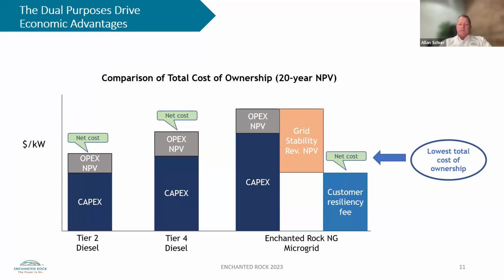The capital equipment for a microgrid is higher, in part because natural gas is inherently more expensive per kilowatt or megawatt of output than diesel, since you need more displacement to get the same power output. All things being equal, no one would ever put in a gas microgrid because the CapEx and OpEx are higher than even tier 4 diesel.